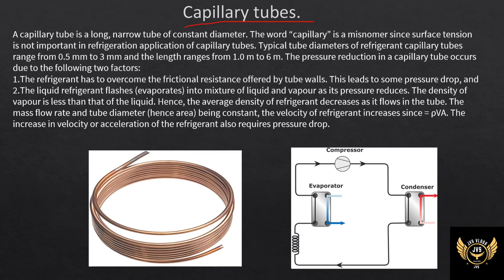Next we have capillary tubes. Capillary tubes are long copper tubes — about 6 meters long with a small diameter of approximately 0.5 to 3 mm. High pressure refrigerant enters the capillary tube. Because it is a long path, the tube creates resistance, which causes pressure reduction.